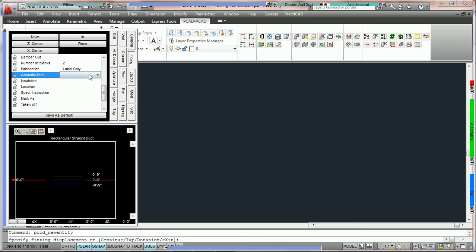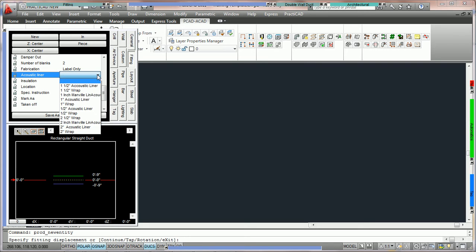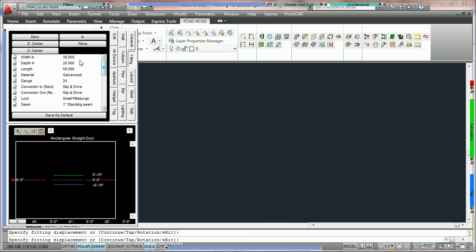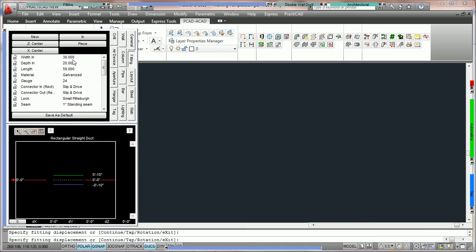So what we're going to do is we're going to go to the acoustic liner. We click right next to it and now we get the drop down menu. Here we're going to see the list of all of our liner types and there are separate tutorials in modifying and designing liner types and styles. What we're going to do here is we're going to choose 1 inch acoustic liner. Once we do that you'll notice that PractiCAD will already have adjusted the width and depth to fit the liner. What was once 36 by 18 when we add 1 inch acoustic liner is now going to be 38 by 20.